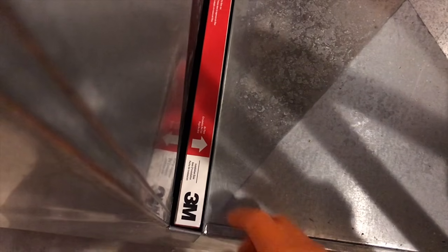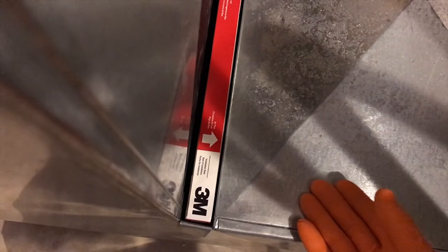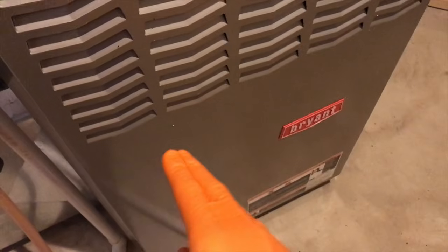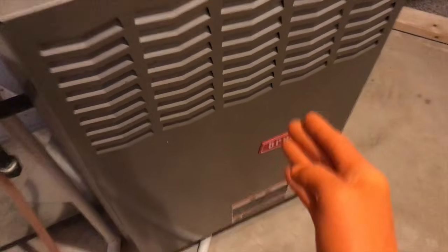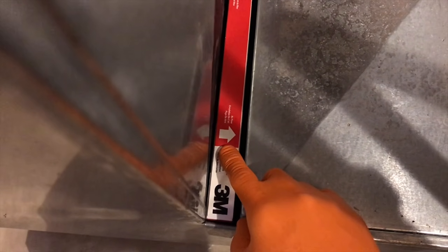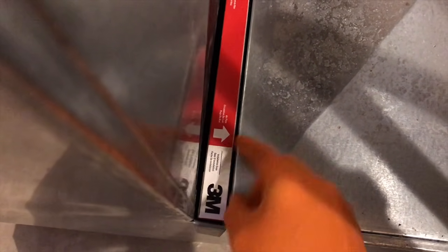However, your fan will continue to blow, meaning all of your inlet air is coming in, which is room temperature, and it's going into the fan blade and motor, and it's being blown out throughout your house into your vents. And during that entire process, your igniter is not lighting the burners, and you are getting no heat whatsoever coming out of your furnace. So if that's the case, make sure you have your filter properly inserted and the arrow is pointing in the direction of the airflow.